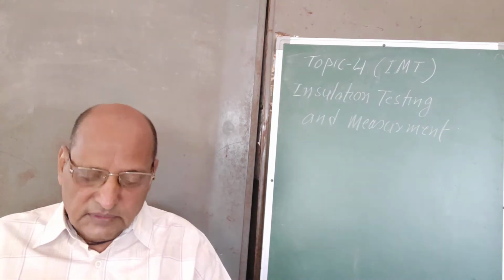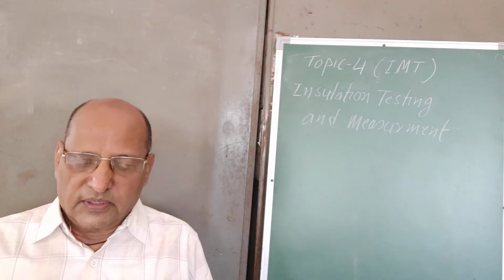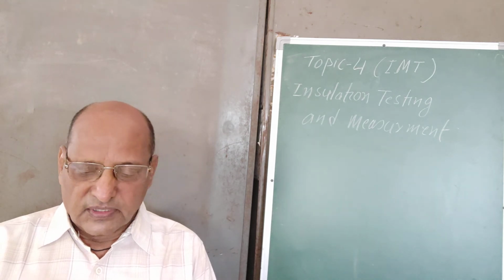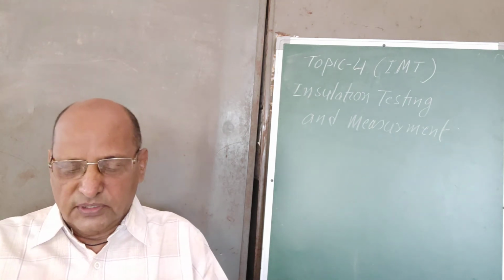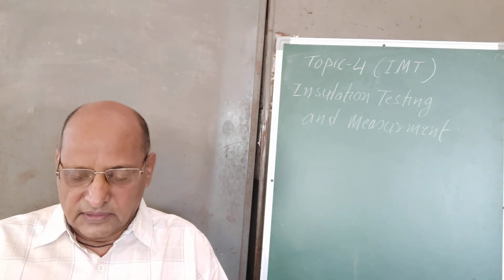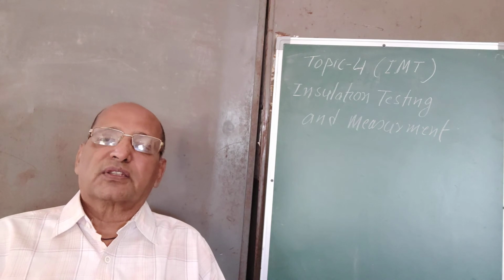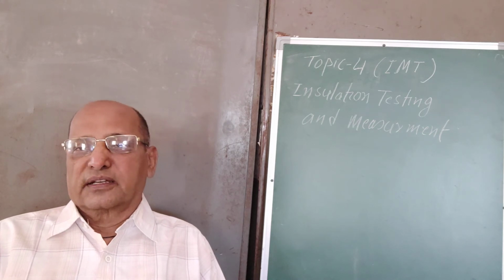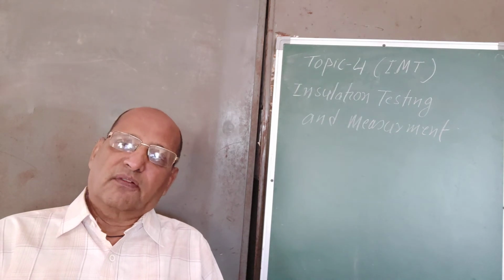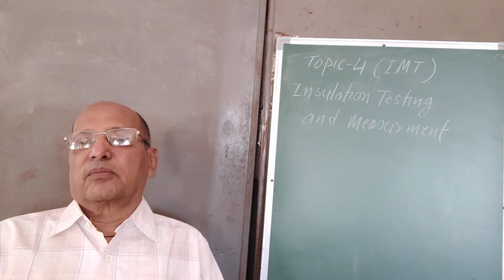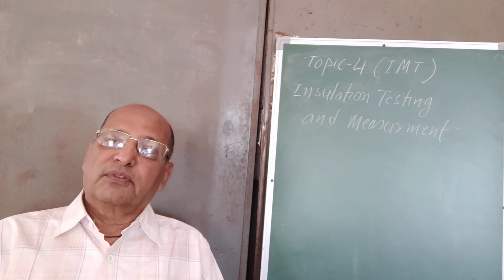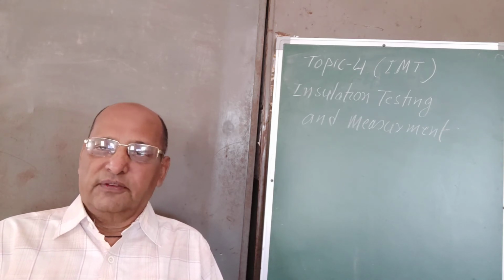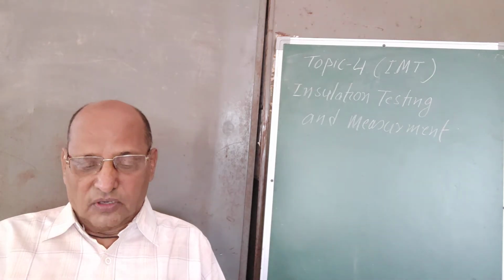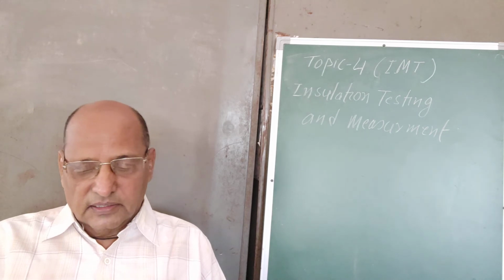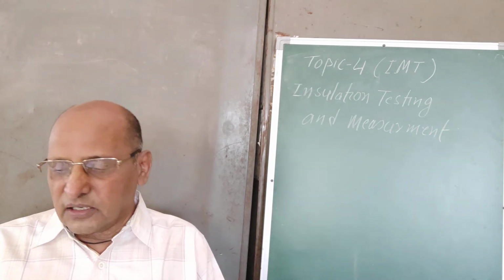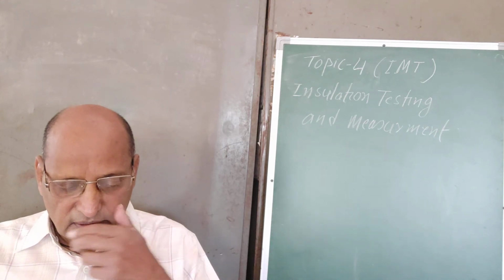So when the value obtained is above 50 kV per centimeter, then we can say that this oil can be reused in the same transformer. If the value is not improved by the number of filtration activities taken on the online filter or the offline filter, if the value of the transformer oil is not improved to what we require, that is above 50 kV per centimeter, then this oil should be removed or replaced by other fresh oil. So these are all the points which I have discussed in this chapter.